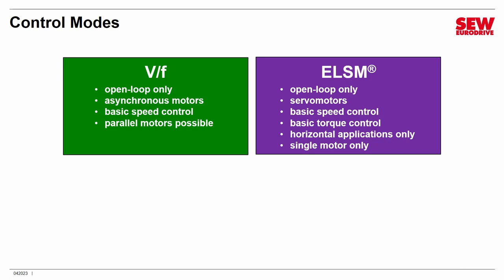There are a few limits in ELSM mode. You cannot do positioning — you can only do speed and torque. You can only use it for horizontal applications; you can't use it for angled or vertical applications, and you cannot put motors in parallel. You can only run a single motor on that VFD axis. But ELSM mode is neat — we'll be playing with it in one of the labs.